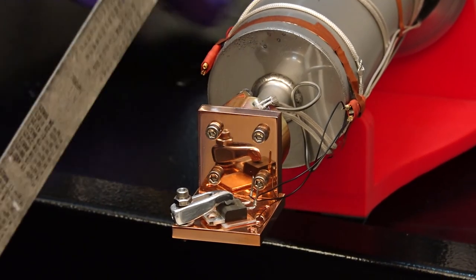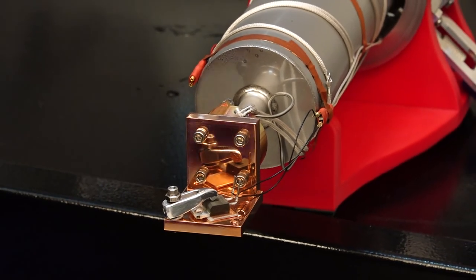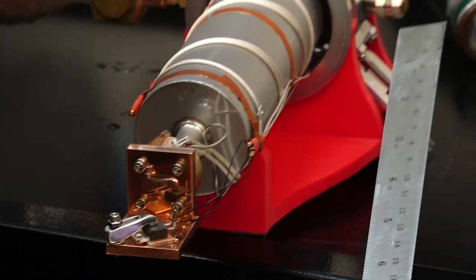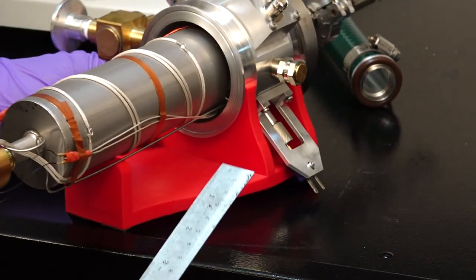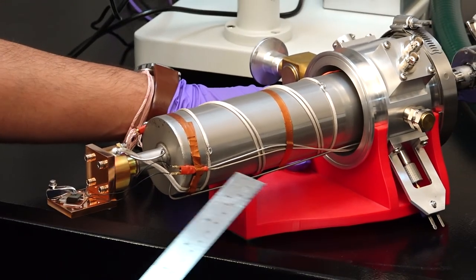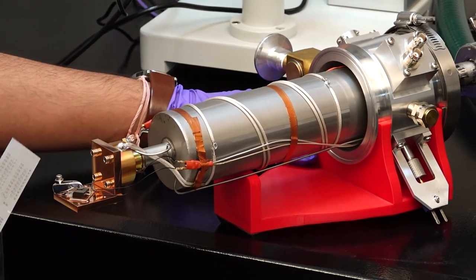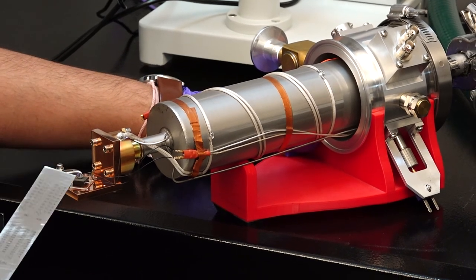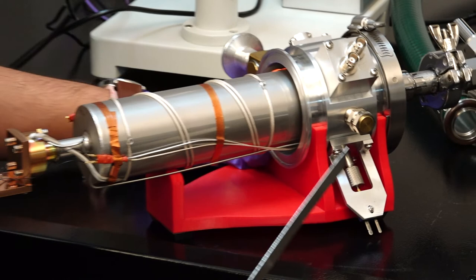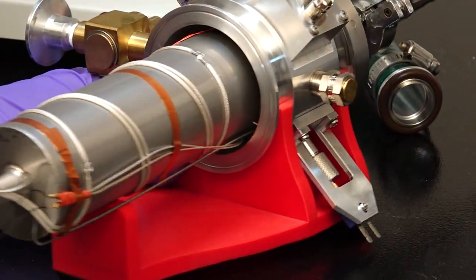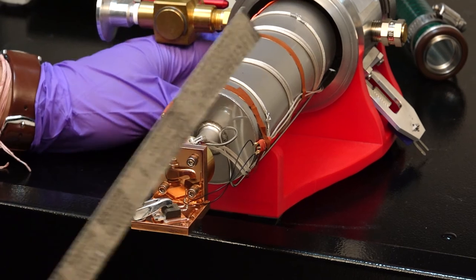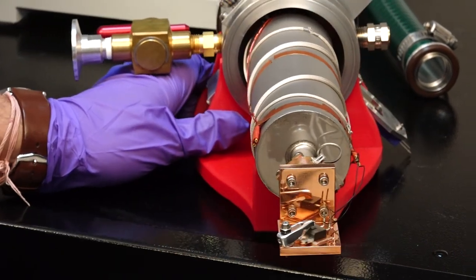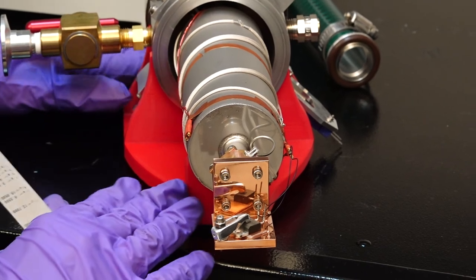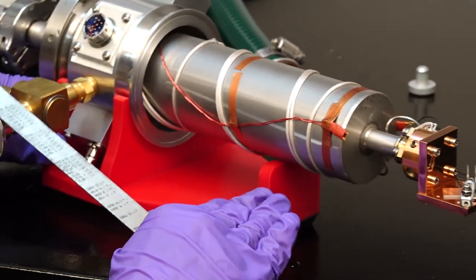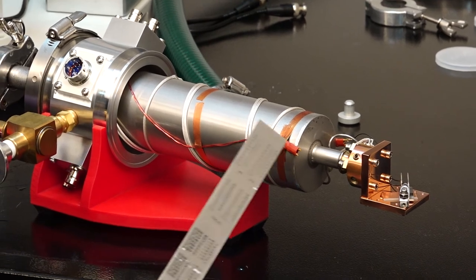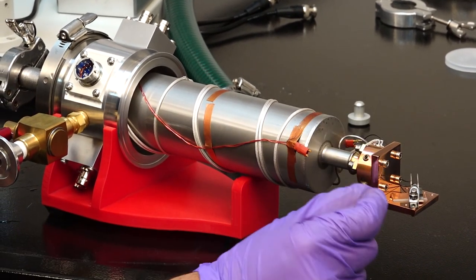First is the thermocouple wire, which takes the temperature from the sample head. Second, these cables that you see convey the electrical signals for capacitance and current measurements to the device, and that port is not visible here, I'll show you later. So this is for the electrical biases. Similarly, for the LED signals, for biasing LEDs and connecting LEDs, we use this port, we attach the LEDs here.